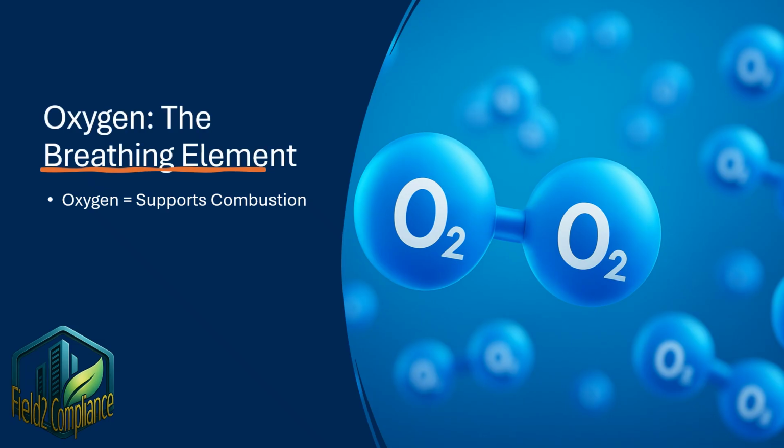Oxygen supports combustion. Fire typically needs at least 16% oxygen in the air to sustain itself. Think of oxygen as the breath the fire takes every second. Control the airflow, smother the space, or interrupt ventilation, and you choke out that fire.